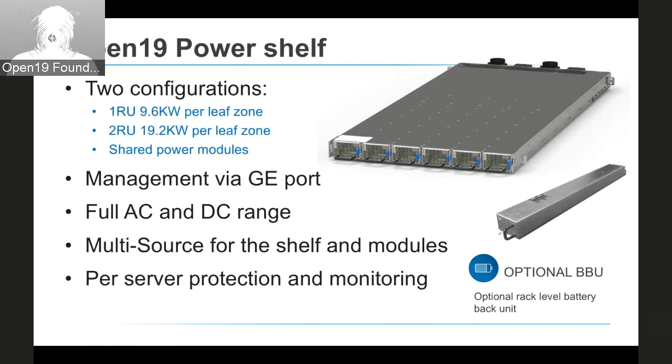It has a management system with a GIGI port. The beauty of this shelf is that it is completely universal. It's universal from an input voltage and an input type. It can go AC/DC on any range that you can have. And it has generic connectors in the back which enable you to only change the whip connection, which means that the whip is the cable which goes from your outlet in the wall or in the ceiling or in the floor into the shelf.